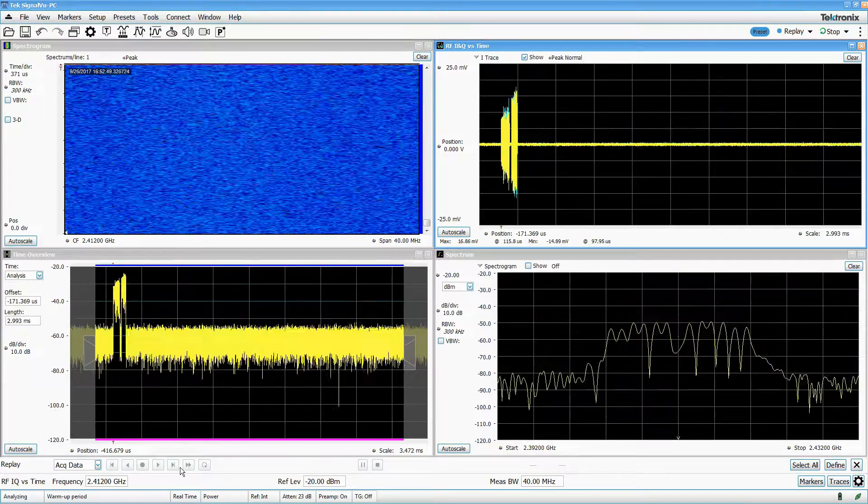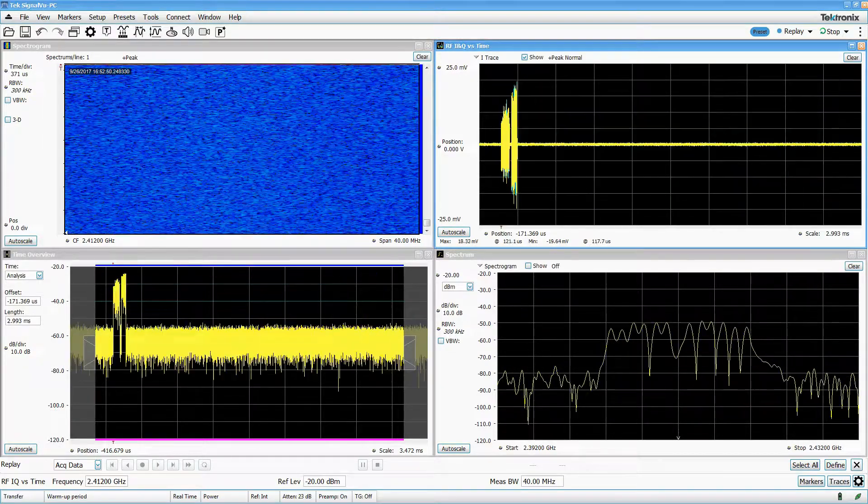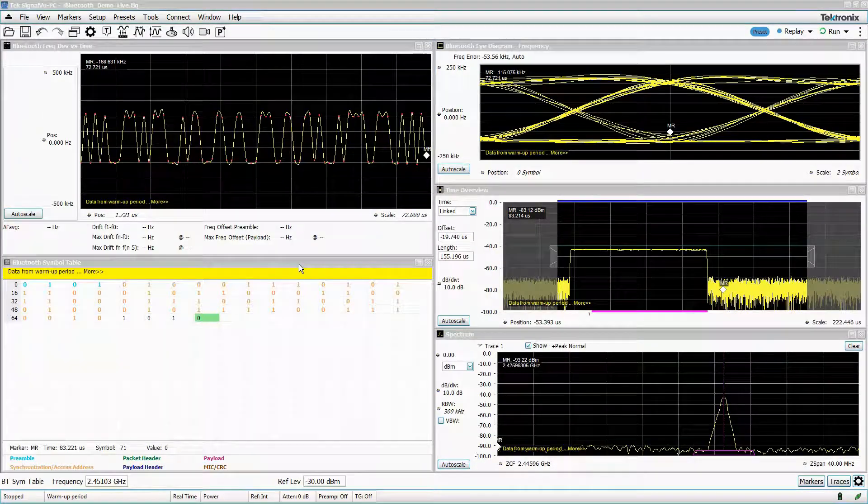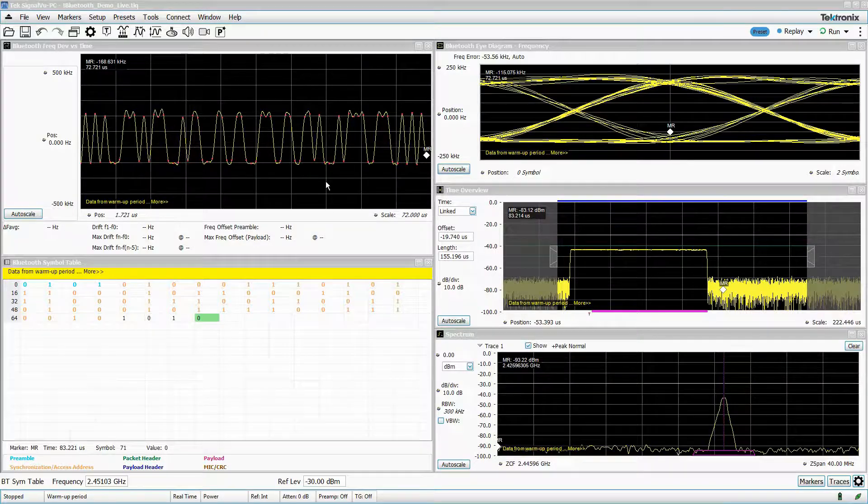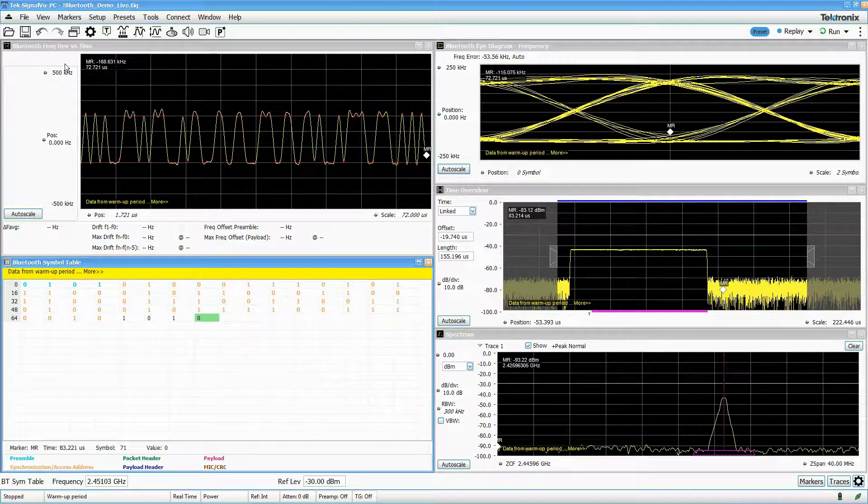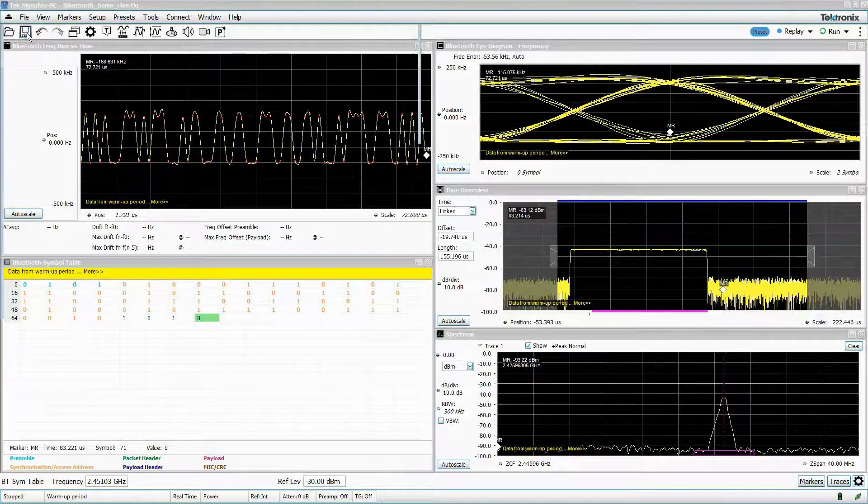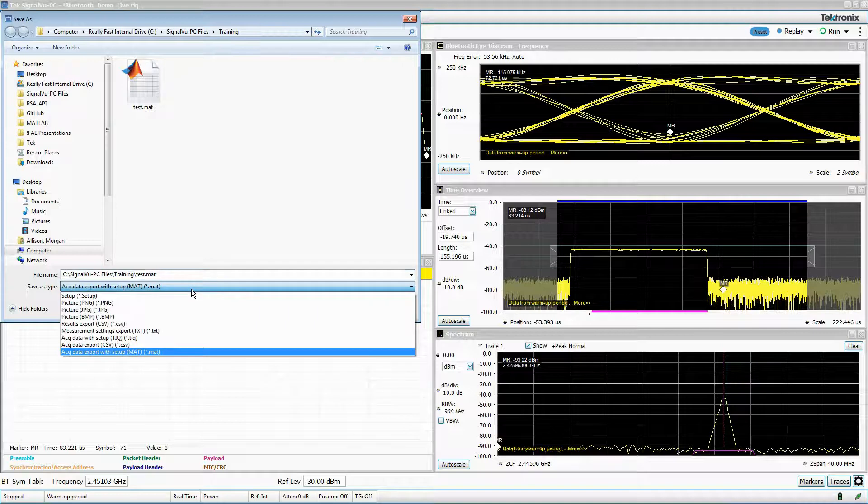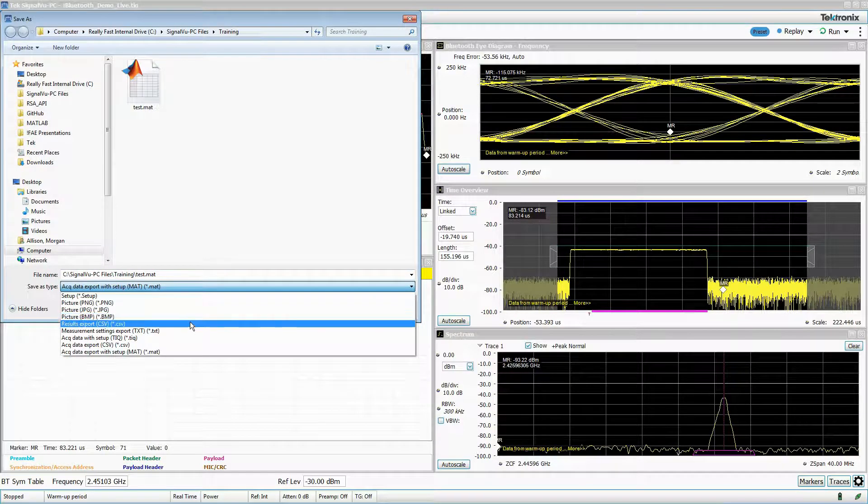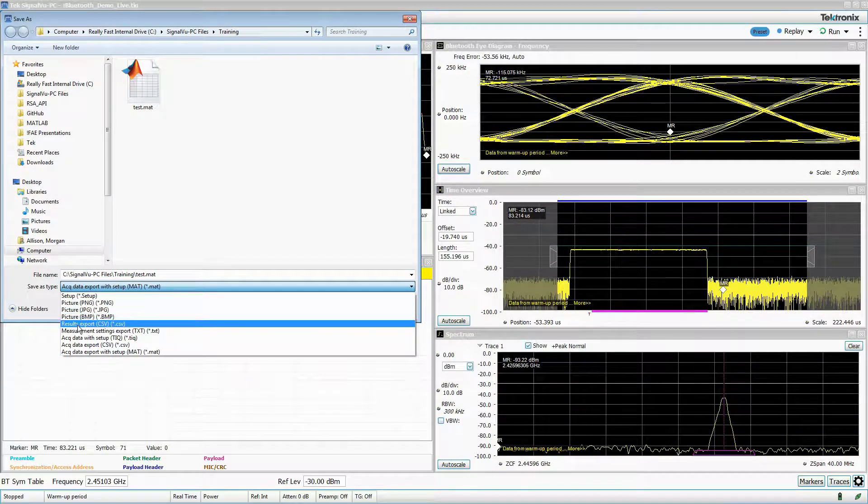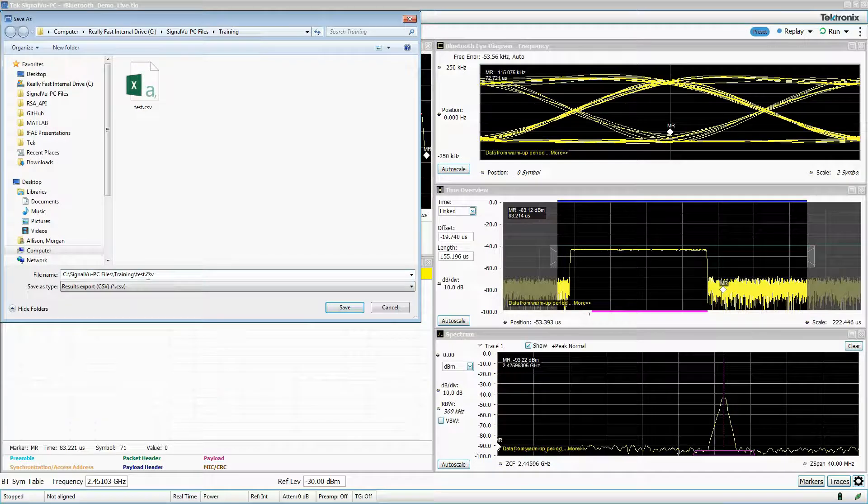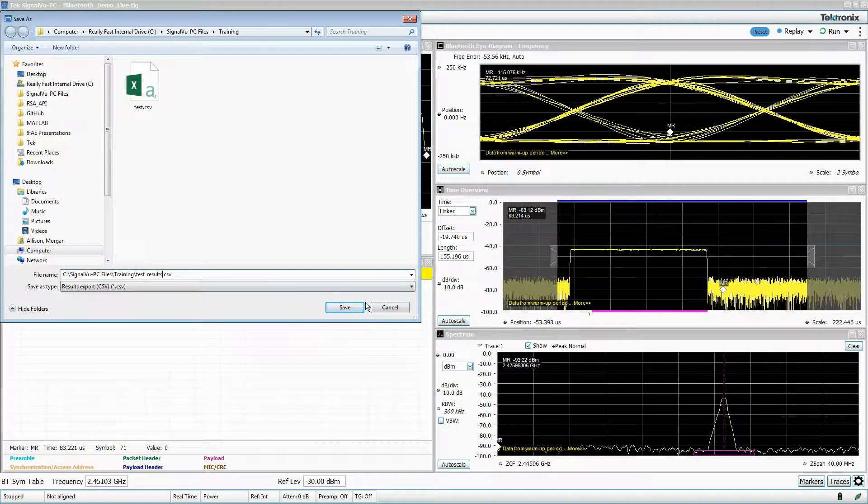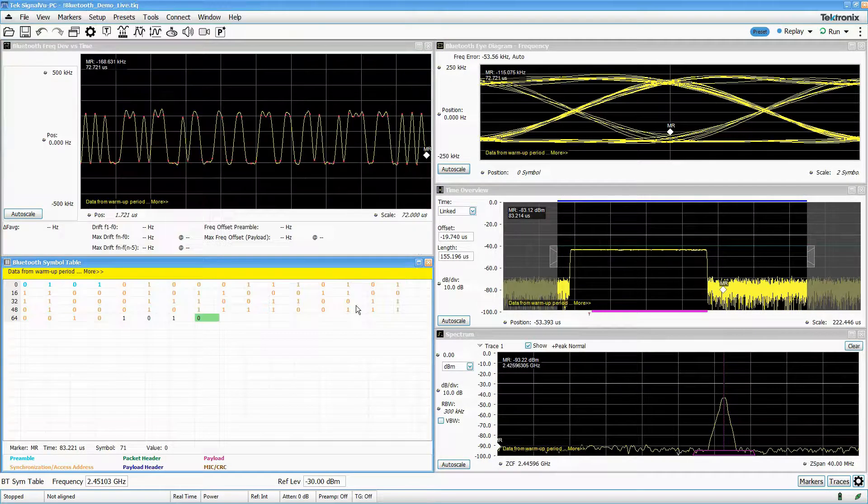You can also export only the measurements of the currently selected display in a .csv file. In the Save dialog box dropdown menu, select Results Export. Note that these files cannot be recalled into SignalVu-PC because they only contain measurement data, not underlying IQ data.